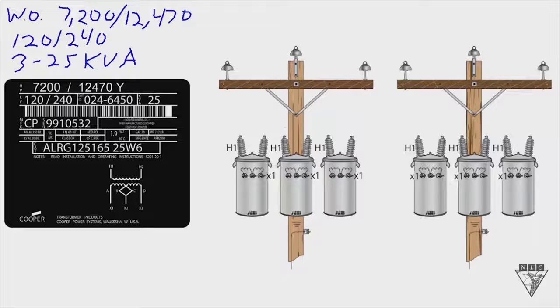So compare this with our transformer nameplate. And on the high voltage rating of the transformer, we've got a match because we've got 7,200 volts, which matches the phase to ground connection on our circuit voltage. Then, if we look at the service voltage, we've got 120/240 on our transformer nameplate, which matches the service voltage required by the customer on the work order.